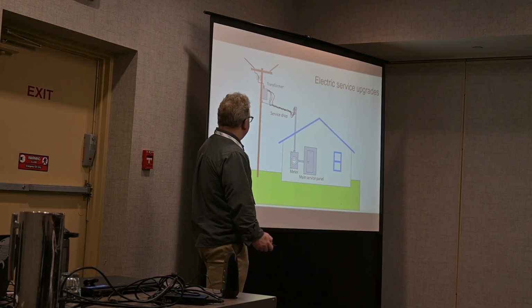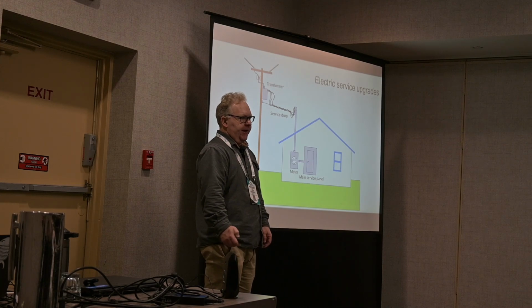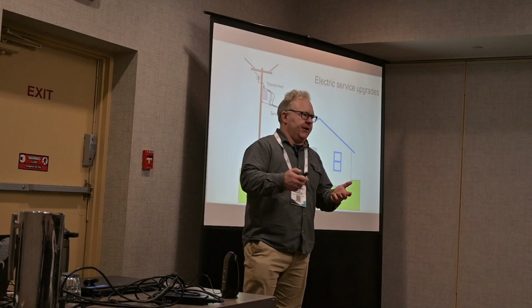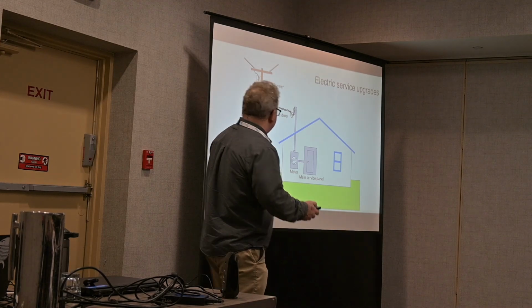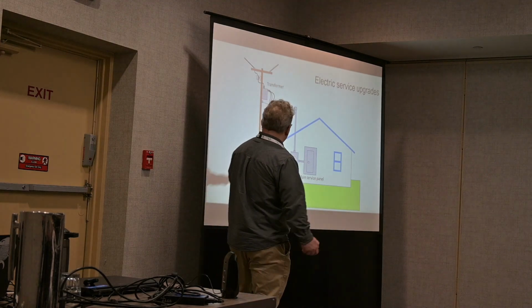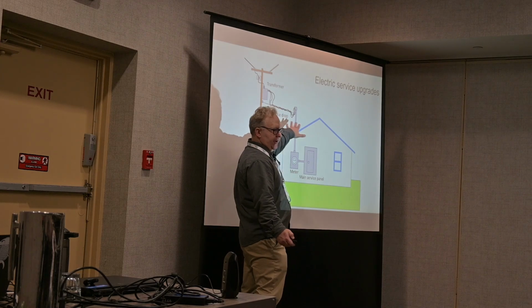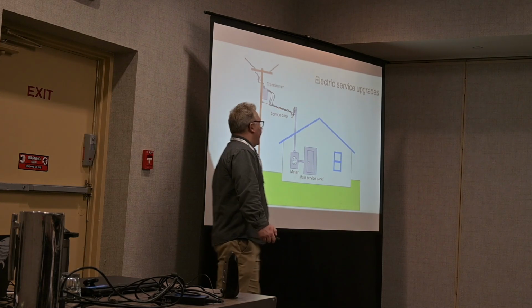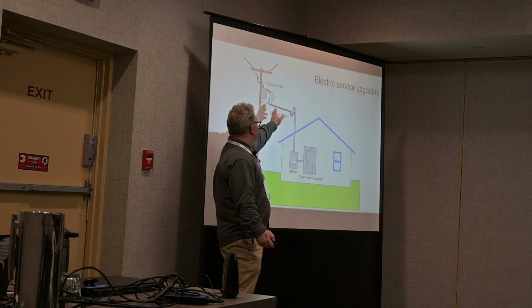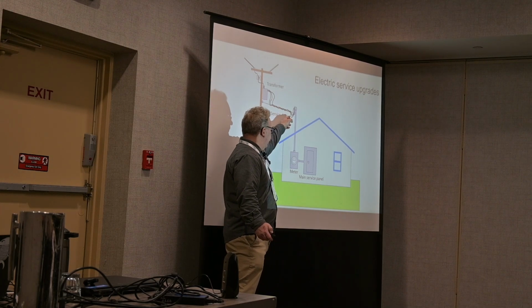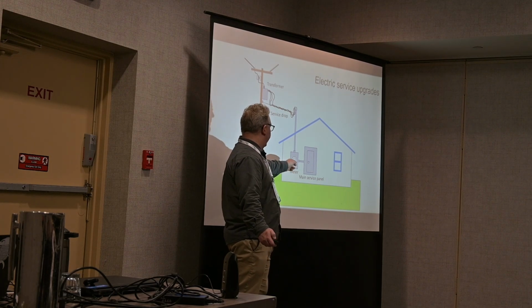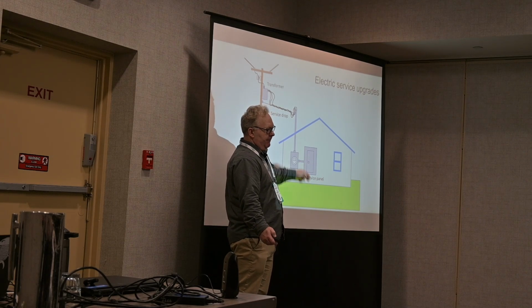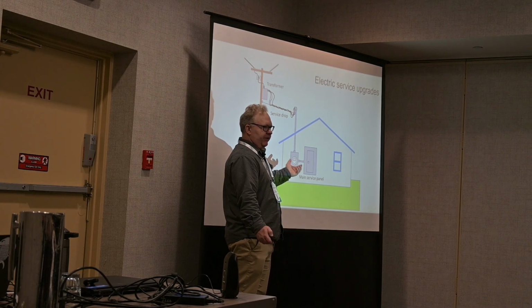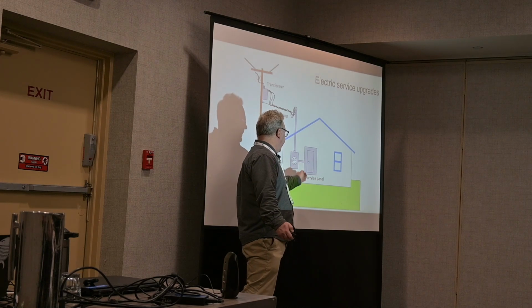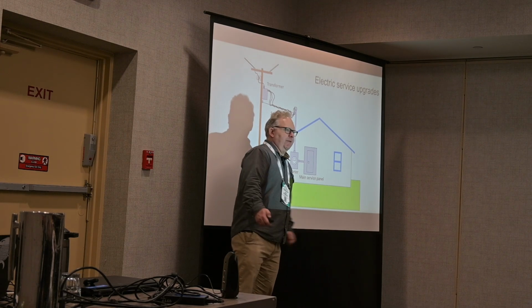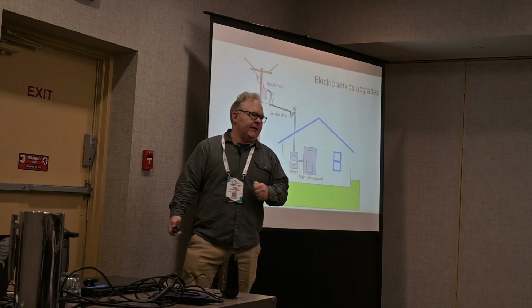Now we can start thinking about electric service upgrades. And as we electrify homes and start adding loads, we may find that the loads that we're adding exceed the rating of our electric service. And so that may require us to upgrade these service conductors. The utility may want to change out the meter. A lot of utilities are in the process of installing smart meters. And we will probably also need to upgrade the main service panel to accommodate those extra loads.